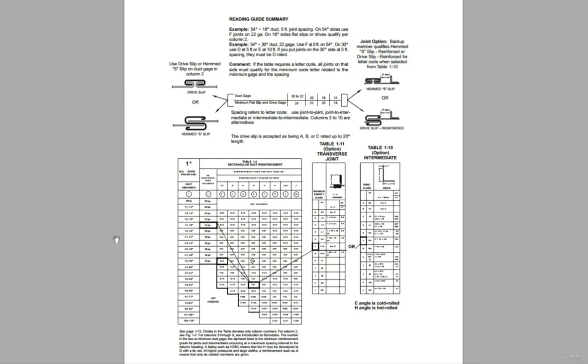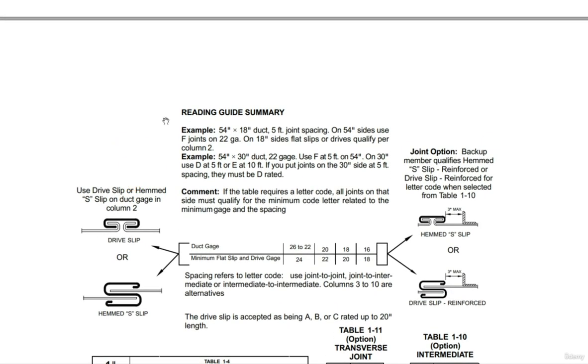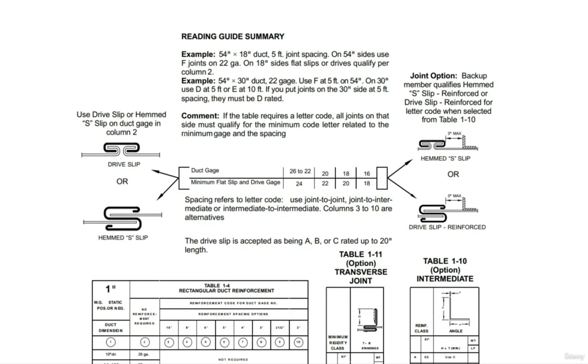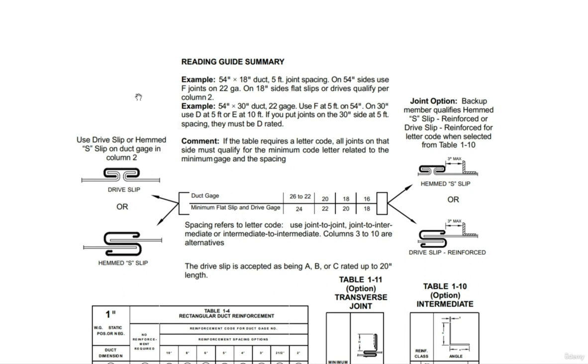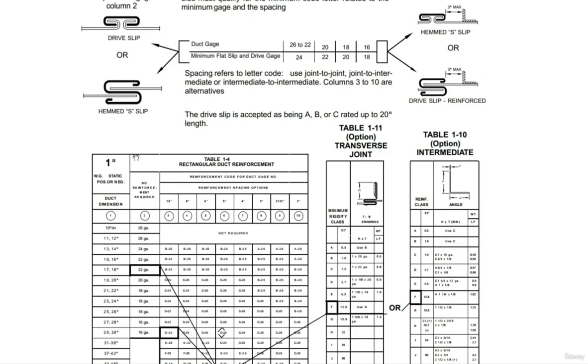Before I explain the presentation, I'm going to walk through an example on how to select reinforcement details from SMACNA itself, using the reading guide summary for these tables. SMACNA has so many tables which can confuse anyone at the beginning. For example, on page 34, the reading guide summary gives an example of a 54-inch by 18-inch duct with a 5-foot joint spacing. This example requires you to specify if the duct needs any reinforcement on both sides — the 54-inch and the 18-inch. Let's explore it for each side of the duct using Table 1.